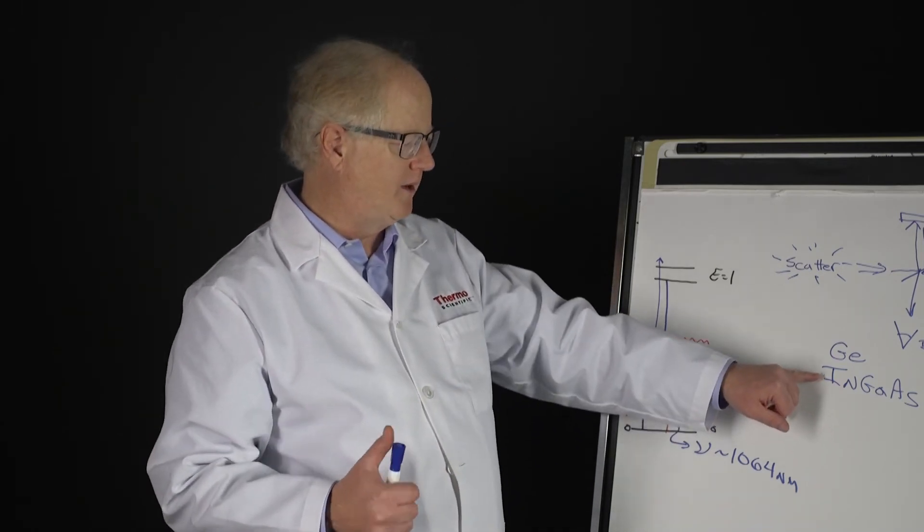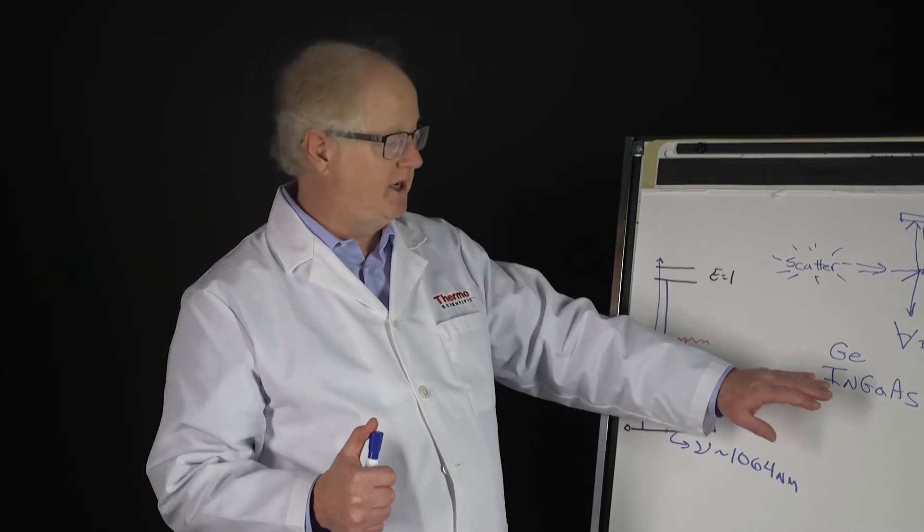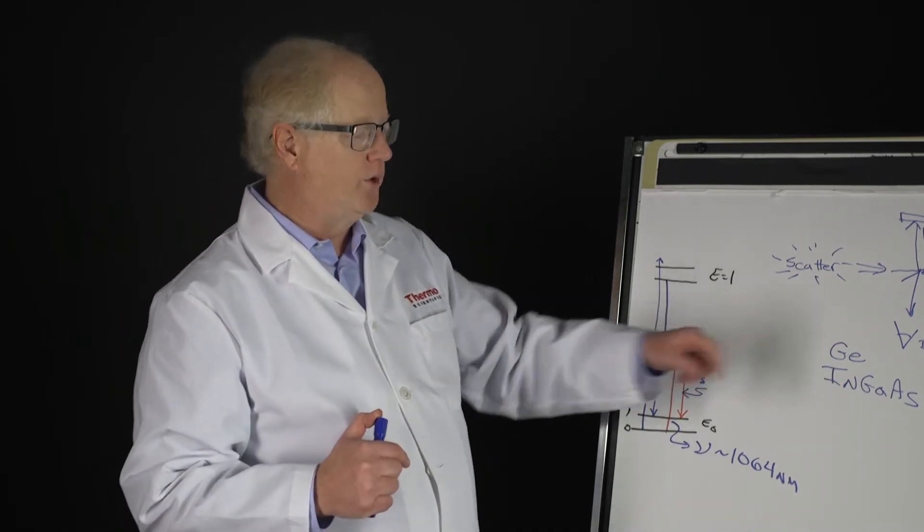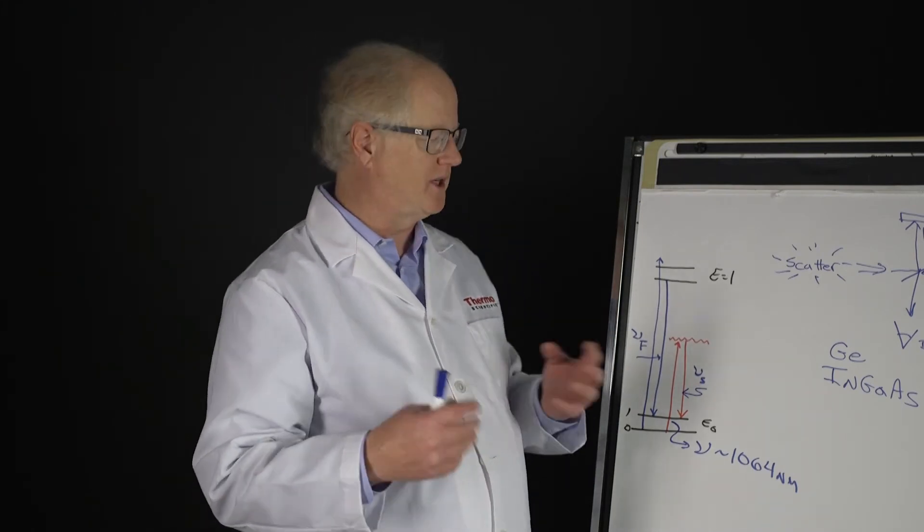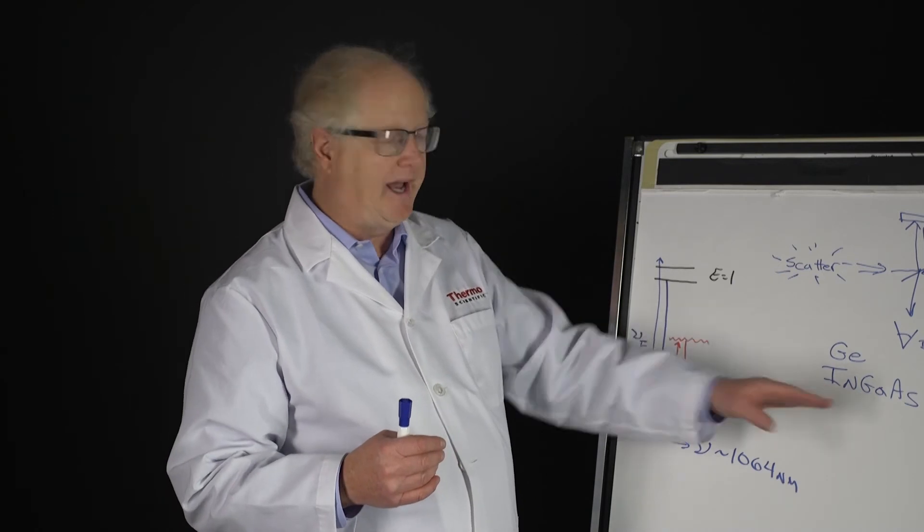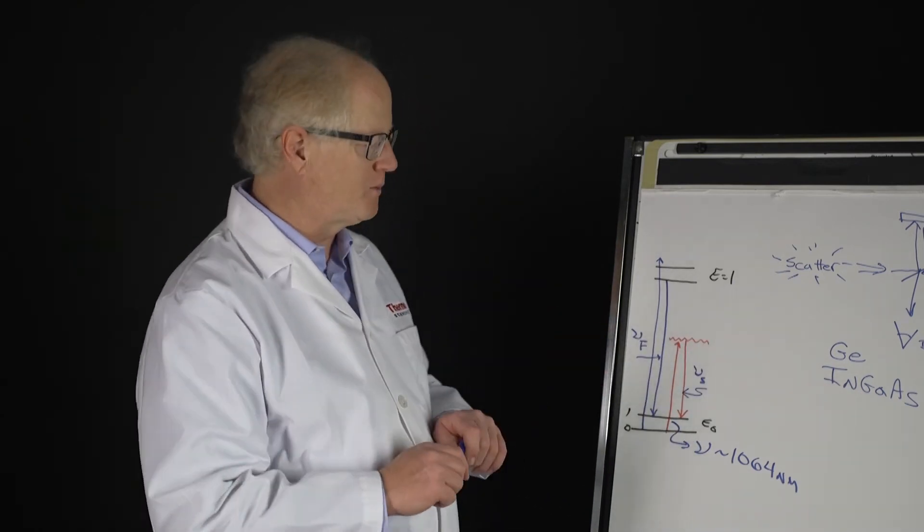With the improvement in the preamps and the improvement of all of the electronics that go with them, the InGaAs detector is almost as sensitive as the germanium. There are very few samples for which you need the germanium detector's extra cost and extra complexity. The InGaAs works just fine for most purposes.